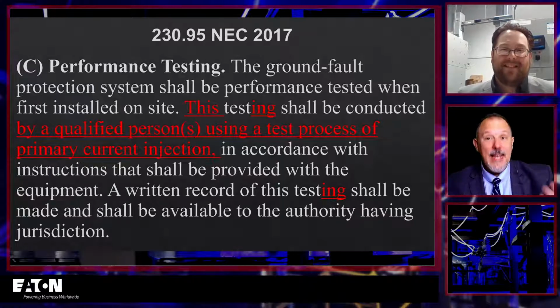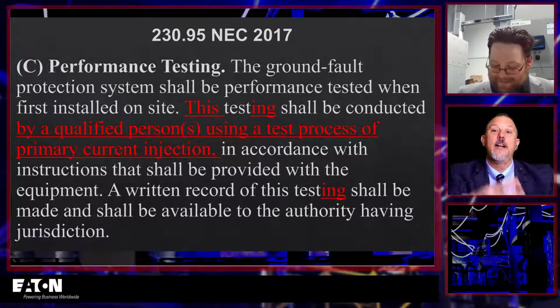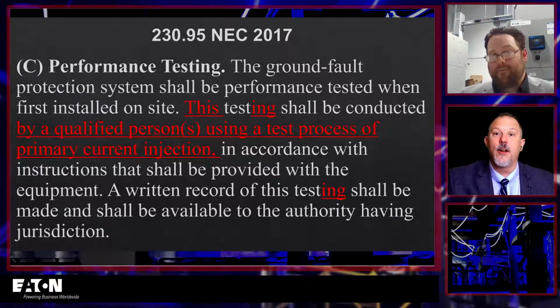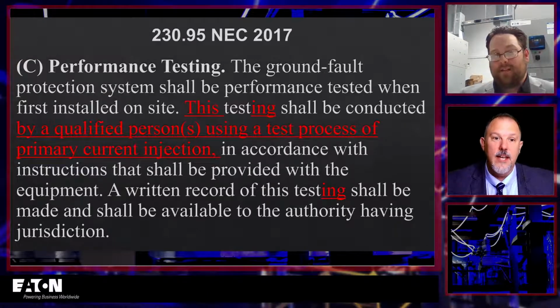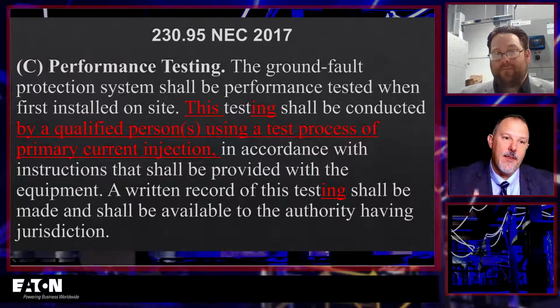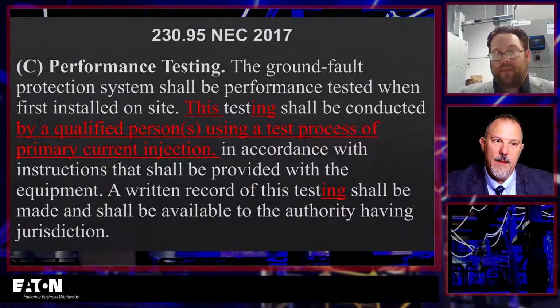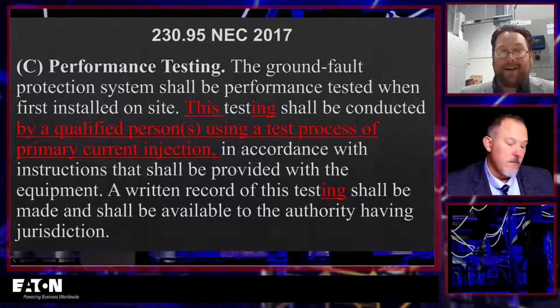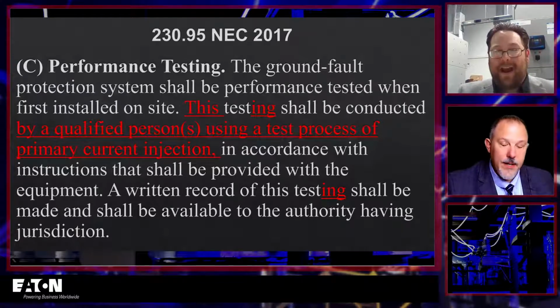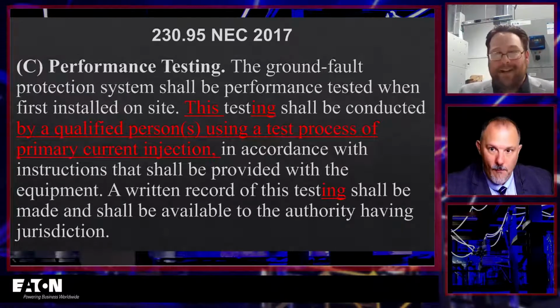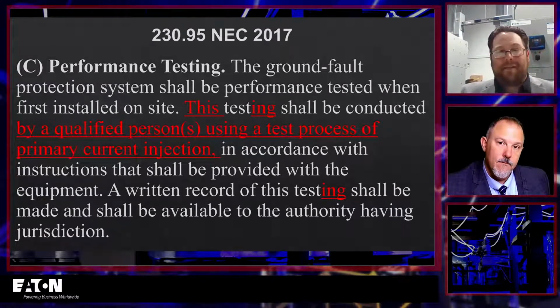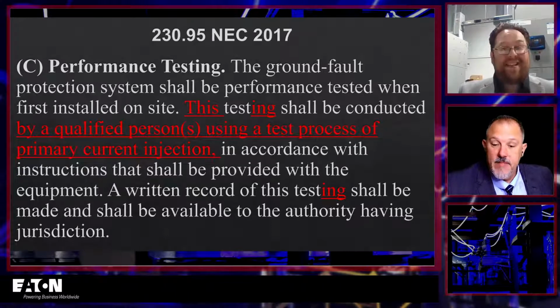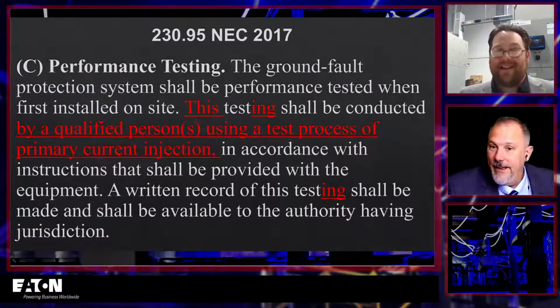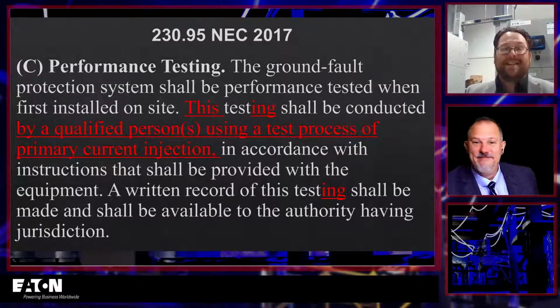Right. So that was two visits, and think about it: all of those wires were terminated. They had to unterminate stuff for him to get his test leads in there. He had to establish an electrically safe work condition. He had to bring his equipment in and everything else associated with getting that job done. And that's expensive and time consuming. Absolutely, and I'm sure that was not just a 1,000 amp service entrance, right? No, it wasn't. That's right. There we had 3 sets of 500 MCM landed on the primary side. Now that was probably a 4,000 amp service, where you have 10 sets per phase to disconnect. Nothing's easy about that. No, not easy at all.